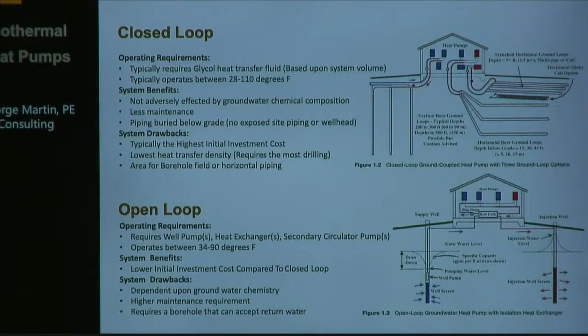For system selection, we're talking about new buildings but also existing buildings. We essentially look at what's there. Heat pumps in general operate at a lower hot water temperature, so for a retrofit that may be designed for a 180-degree boiler, we really have to take that into consideration. Obviously a new build isn't as much of a consideration, but we do want to assess if there's something that can be reused with this technology.